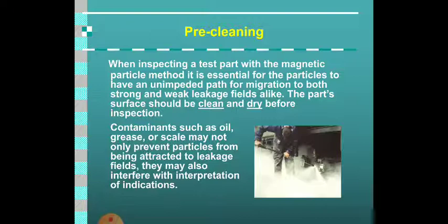The first is pre-cleaning, which is required; in almost every condition, most NDT techniques go through pre-cleaning. When inspecting a test part with the magnetic particle method, it is essential for the particles to have an unimpeded path for migration to both strong and weak leakage fields alike, so the part surface should be clean and dry before the inspection.